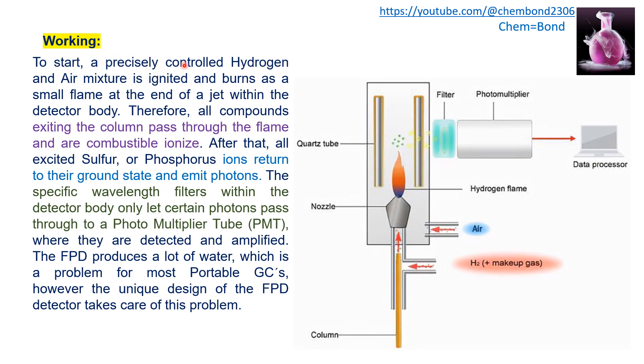For working of the FPD, a hydrogen flame is produced by the ignition of a hydrogen and air mixture. The column effluent containing sulfur and phosphorus moves towards the flame and combustively ionizes, moving sulfur and phosphorus compounds to the excited state. When these return to the ground state, they emit characteristic photons. Specific filters allow these photons to reach the photomultiplier tube, where they are amplified and detected. A drawback of this detector is that it produces a lot of water, which is problematic for GC detectors. However, newer FPD designs minimize or eliminate this problem.